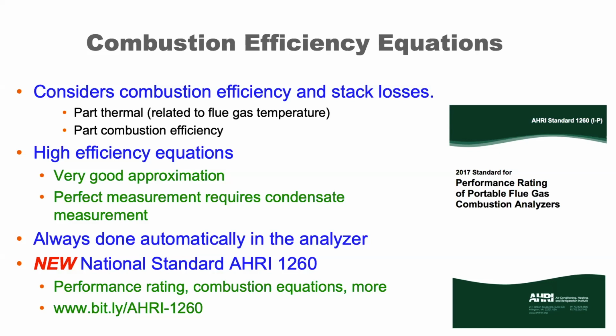And these are always automatically done in the analyzer. It used to be that you had to look them up and use a slide rule calculator, and that dates back probably 30 years. But now they're all done. You get the combustion efficiency. And this new standard, you can check to see if your analyzer is compliant with the standard.